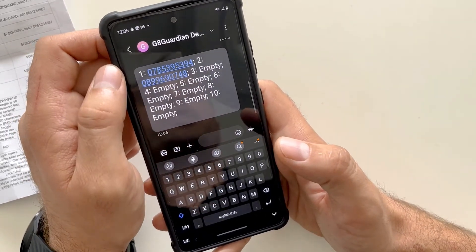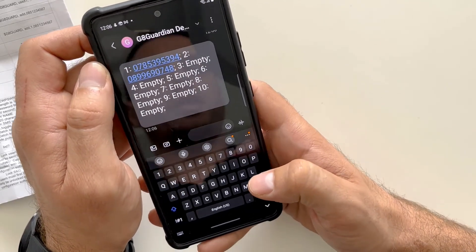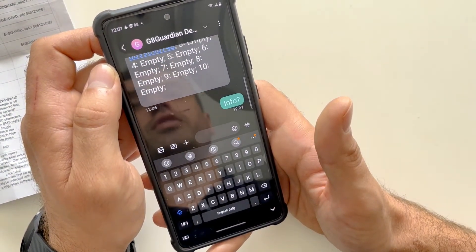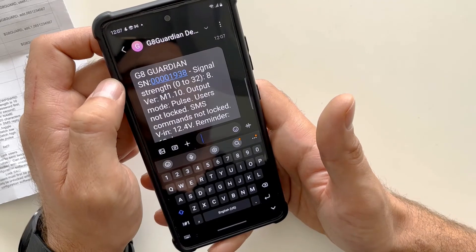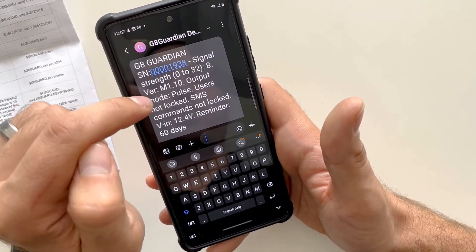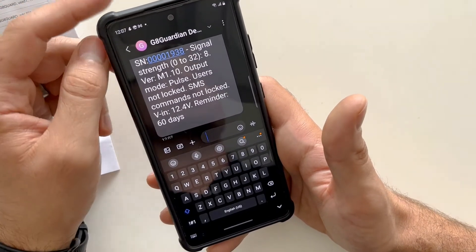While on site, this is great for installation technicians or homeowners installing the device. Type the command: INFO? — info followed by a question mark. This will request all information pertaining to the G8 Guardian such as signal strength, software version, and the mode of the relay. As you can see, we've got the G8 Guardian with its serial number, a signal strength from 0 to 32 — ours is 8 which is quite low — software version 1.10, and the output mode of the device is in pulse, which is ideally what you want for gate motors.